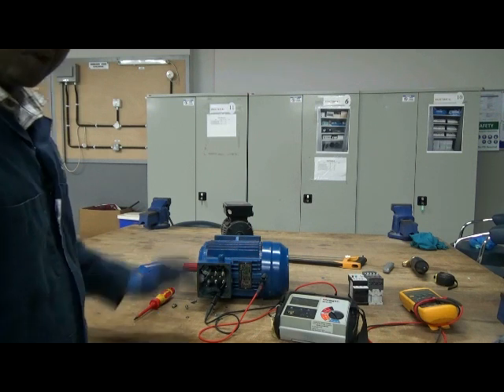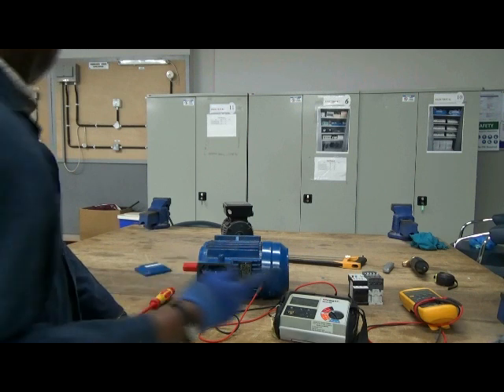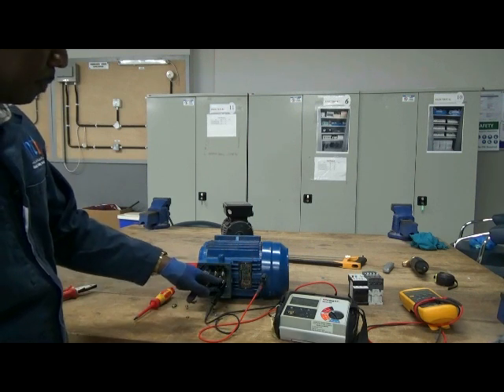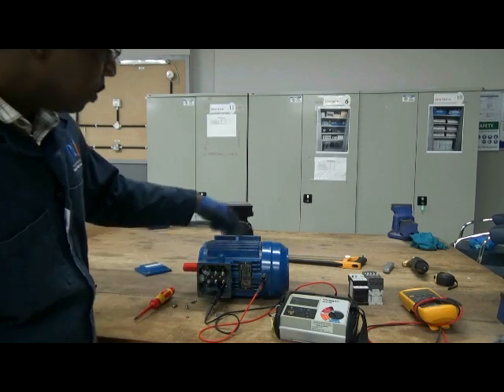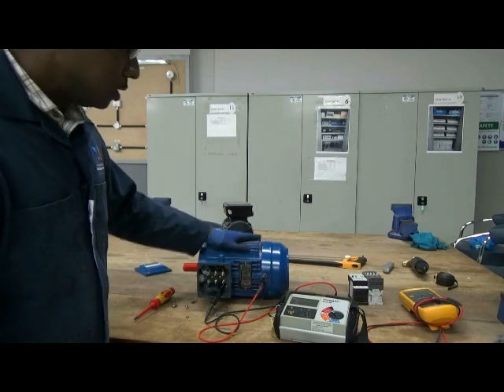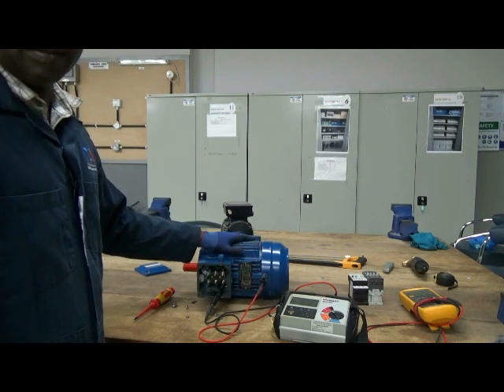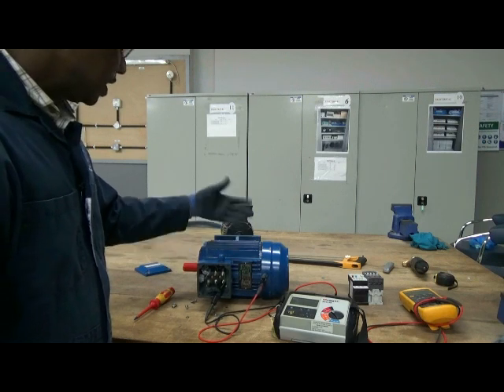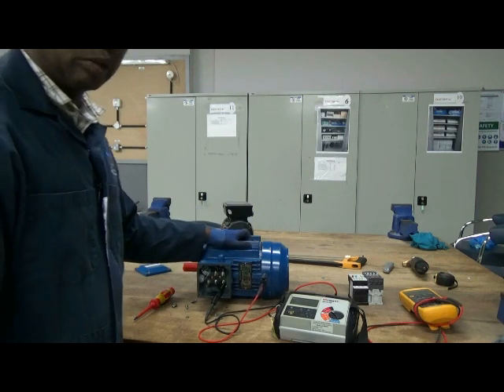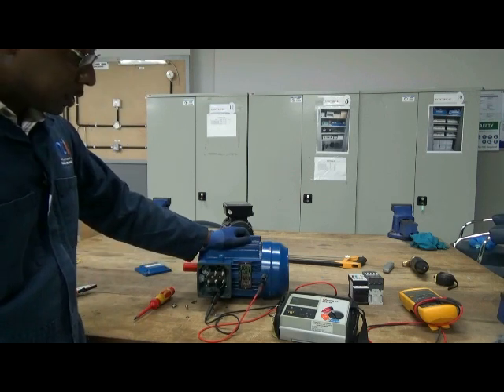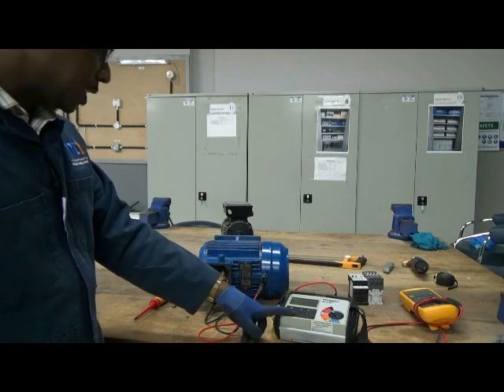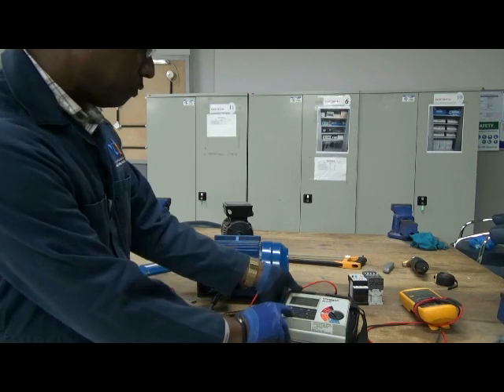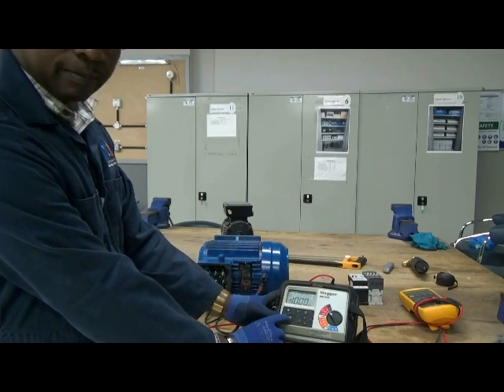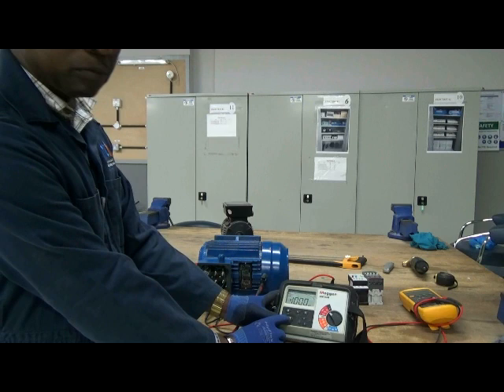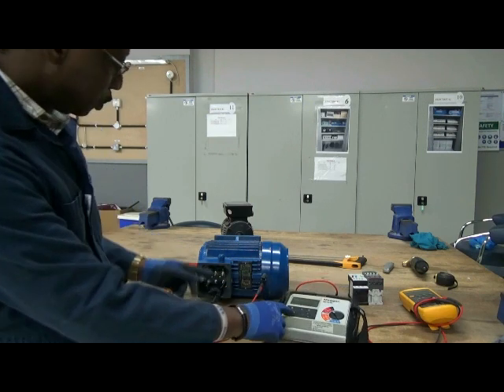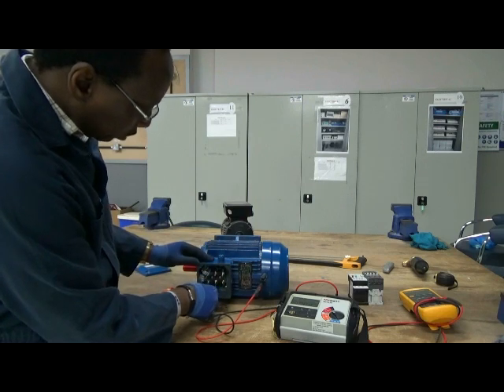If it is not, then the machine would not be able to be connected to the supply. Because if you connect your supply onto this first winding here, then current will be able to flow and come out through the earth point, and we don't want that, because people who are carrying out maintenance normally touch these machines when they are running. So if the insulation resistance is bad, then they might receive some shocks. Once again I'll press my test button, and it is giving me a reading of bigger than 1,000 mega ohms. Very good insulation resistance between that winding and the ground or earth.